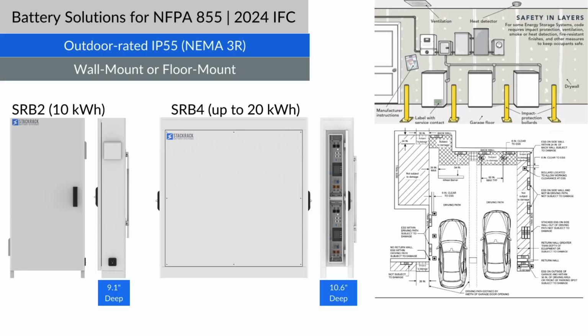Let's talk now about battery solutions for NFPA 855 and 2024 IFC. This comes into play in certain installations where certain AHJs or cities just don't want more than 20 kilowatt hours in a single enclosure, or if the project or installation has very minimal setbacks, and you're trying to get these systems on the wall or reduce the amount of exposure off the wall as much as possible. In these situations, that's where the SRB2 and the SRB4 really come into play.